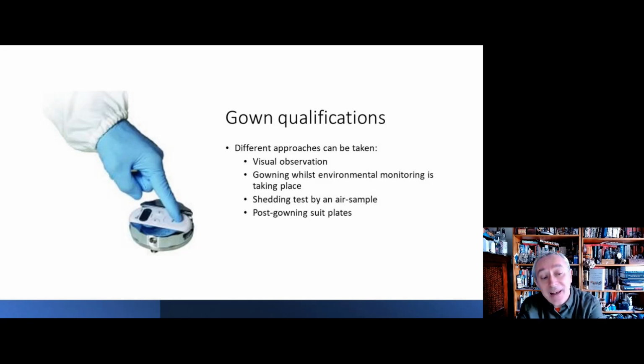Every time anyone leaves the aseptic filling suite, they have contact plates taken on their gowns, which is an assessment of the gown cleanliness, which is showing what might be a contamination risk, or what may have been a contamination risk, and also how well the people are behaving, wearing and respecting the gown as well. So there are samples taken, for example, of the top of the head, from a forearm and from the body torso, and we seek where possible for those to be taken independently.